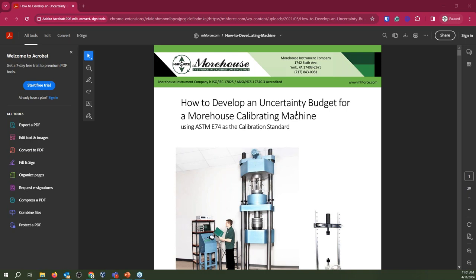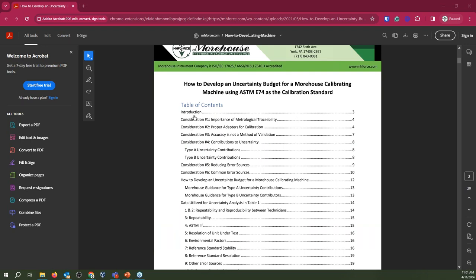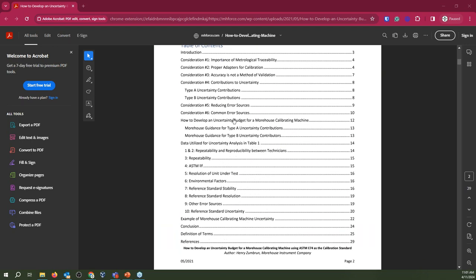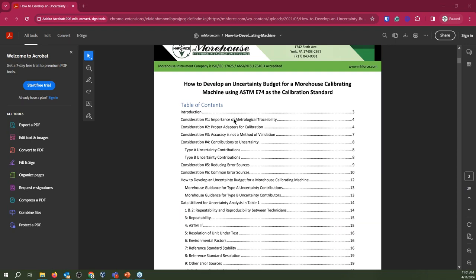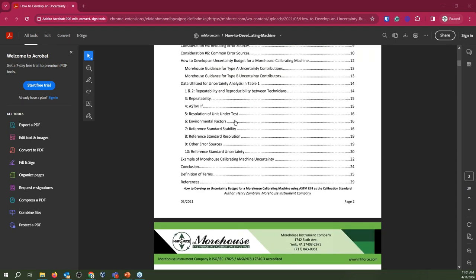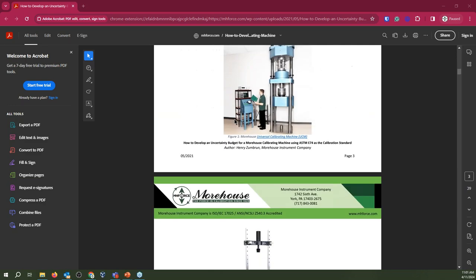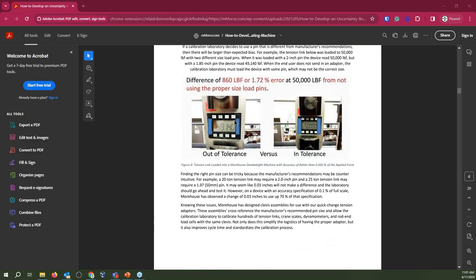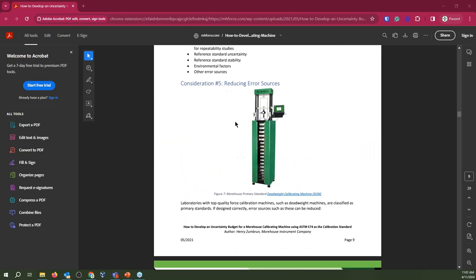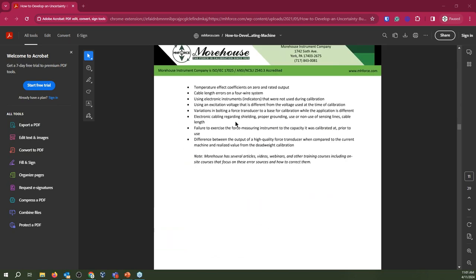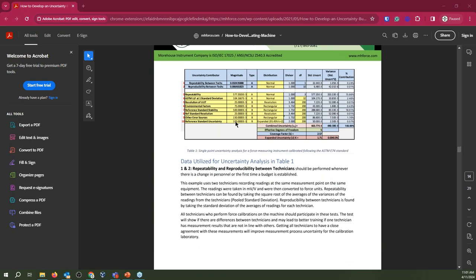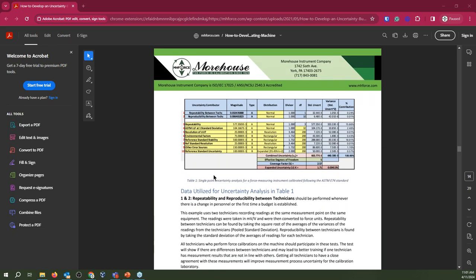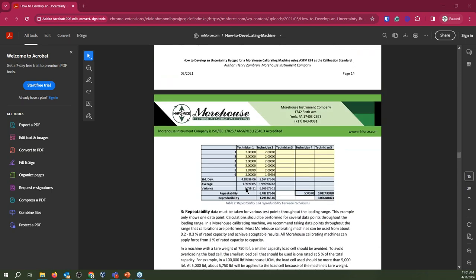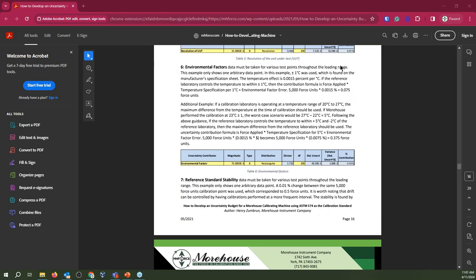This one is how to develop an uncertainty budget for Morehouse UCM. And you can see all that's going on here: considerations, different things, ASTM lower limit factor, reference standard. It goes over basically a lot of the stuff we went over today and how to do it as well. There are some budgets, 1, 2, 3, explaining them all. Repeatability and reproducibility between technicians should be performed whether it's a change of personnel. It just gives you a lot of good guidance to creating that uncertainty budget.